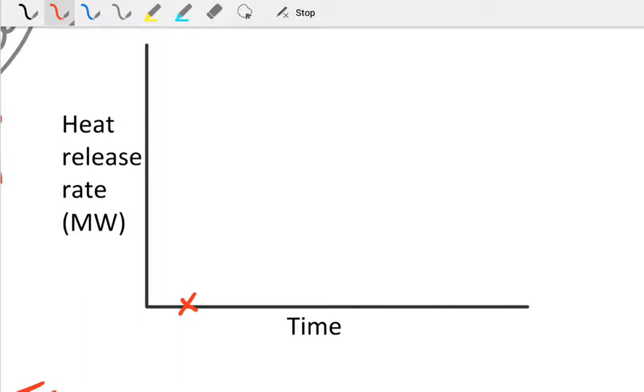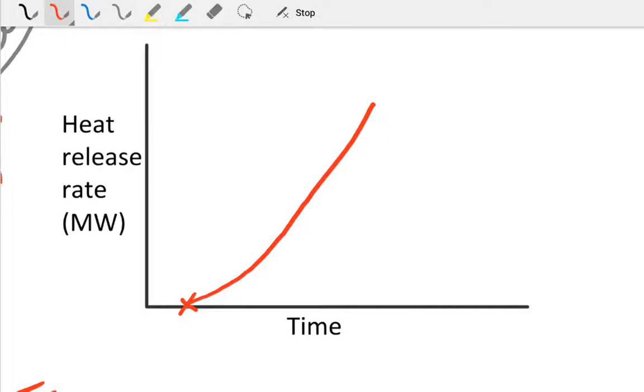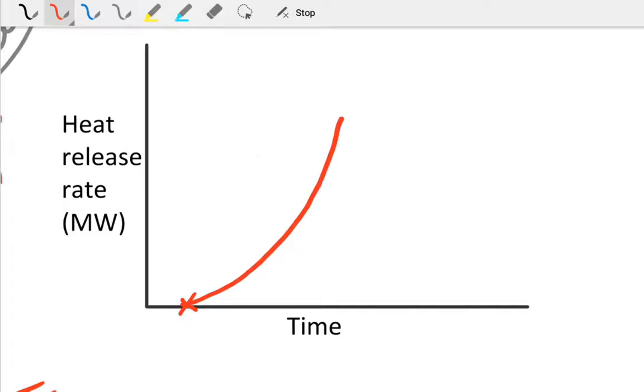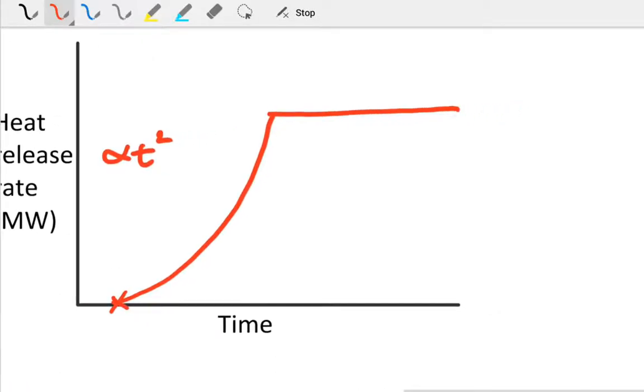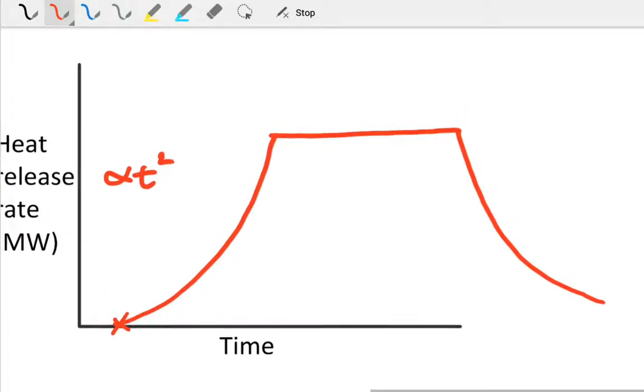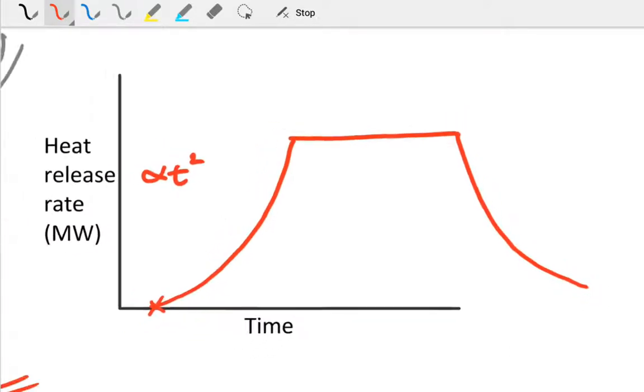Then it'll develop right through to a number of megawatts—5, 10 megawatts. Train carriages and other things may be 50 megawatts or higher. So this is a t-squared fire, a sort of t-squared value up there. The heat release rate is proportional to some constant times t squared, and then it flat lines as controlled by ventilation and then goes down. This is a very simplified representation of the heat release rate, but it gives a reasonable approximation of what's happening depending on various parameters.